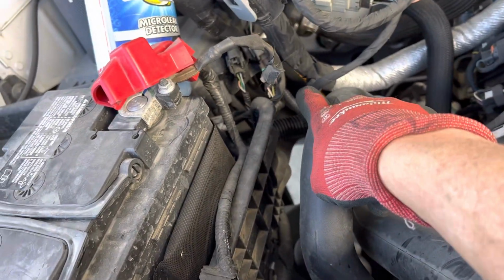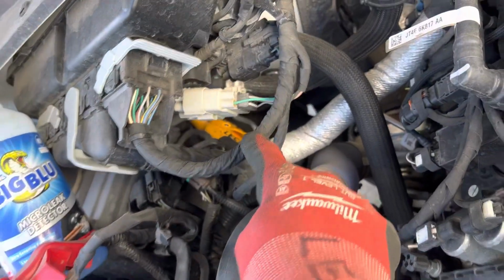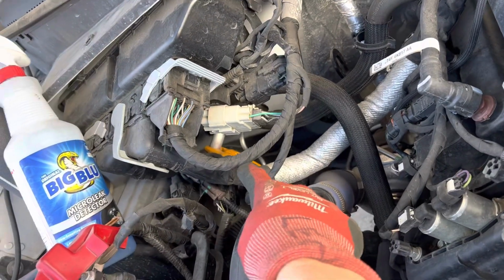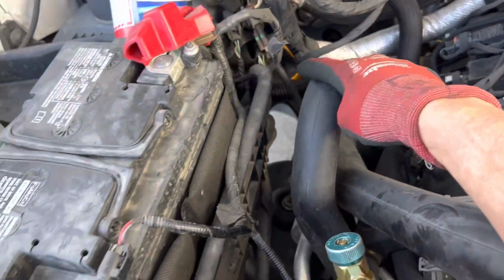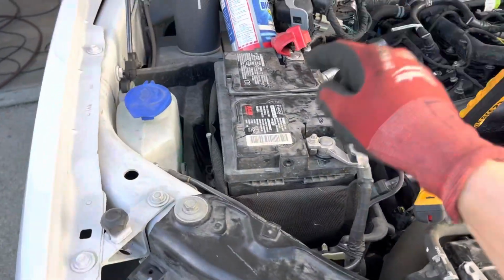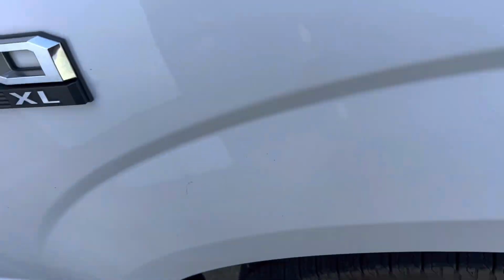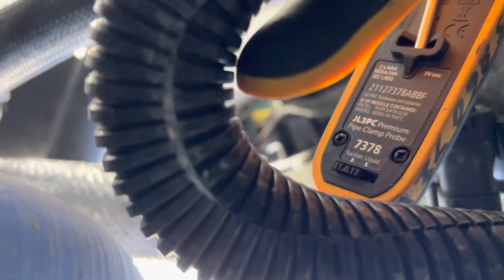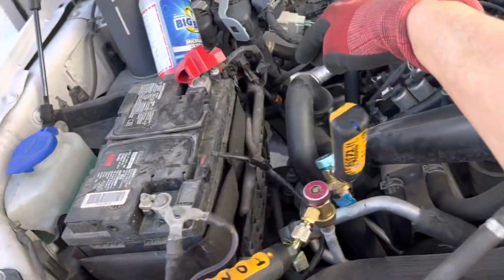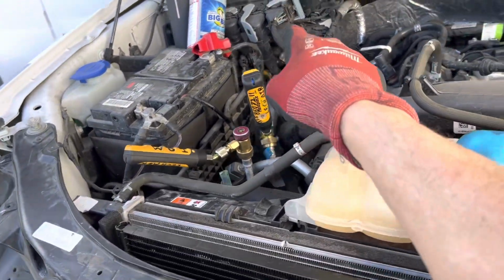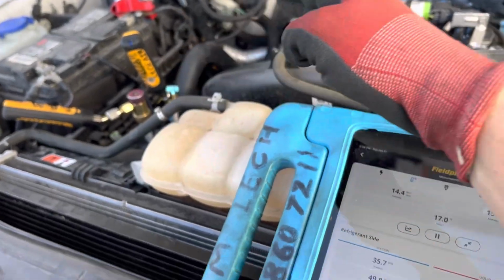You could see my temperature probe, the yellow probe right there that you can barely see. I'm on the suction line coming out of the evaporator, but just after that, a few inches, is where the liquid line comes back out of the internal heat exchanger. Let's see if I could get you a better view down here. Okay, that's my temperature probe, but I can't really get you a good view of what you need to see, but it Y's out of there. So we're going to pay attention to the temperature of the suction line coming out of the evaporator.